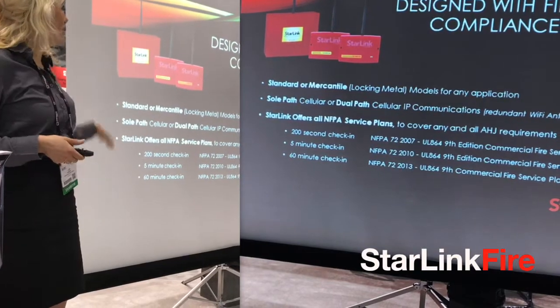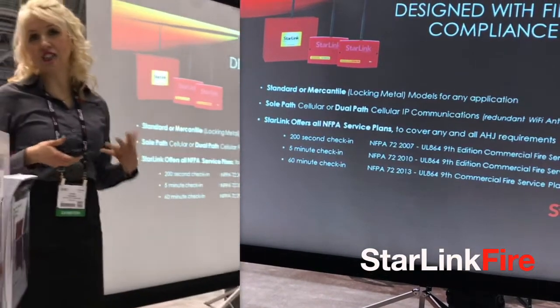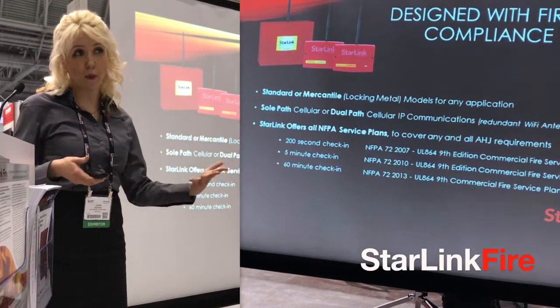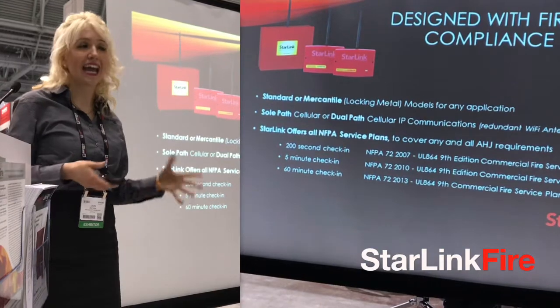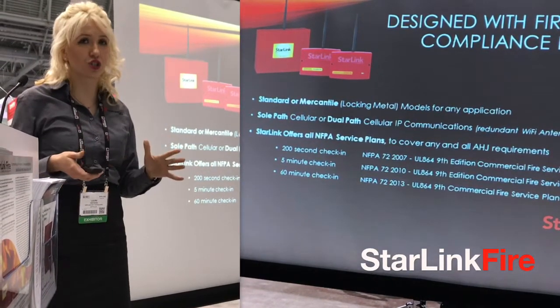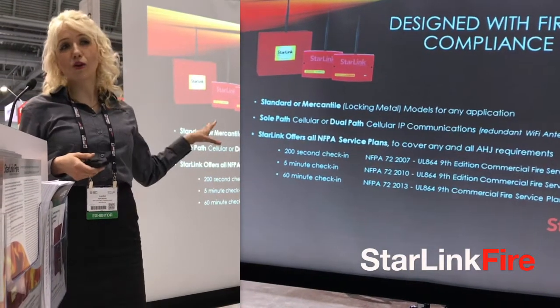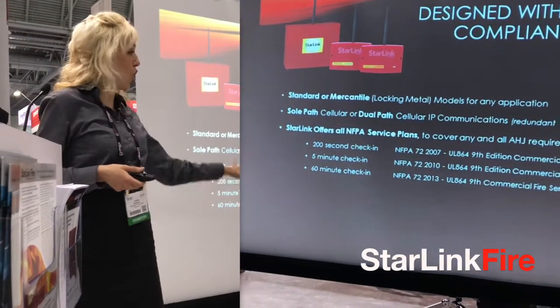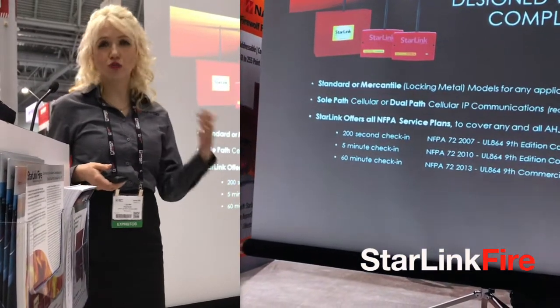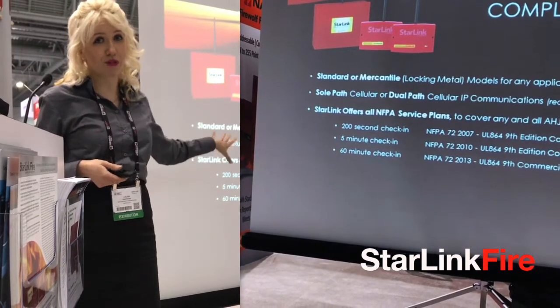Here you can see both the standard and the mercantile style of Fire models. Both of them come in either Sole Path or Dual Path models. They also combine cellular and IP reporting for extra security, as well as to meet some regional requirements. Likewise, Starlink flexibly offers all NFPA service plans for any AHJ, from 200-second check-in to 60-minute ones. Very versatile.